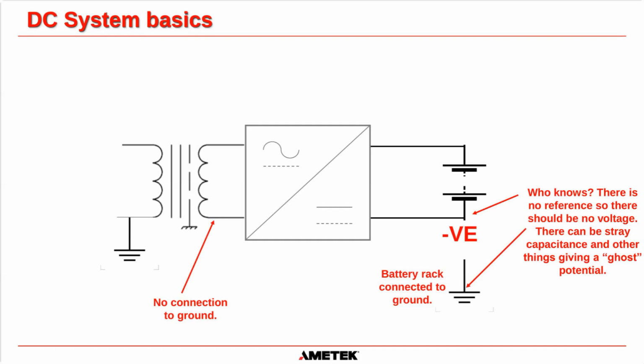And before I do move on, one more reason for why we do this is, remember, battery maintenance is an important part of plant maintenance. So there are going to be people who go out on a quarterly, 6-monthly, annual basis and touch your battery and maintain your battery. Okay, so if they're exposing themselves to the terminals on the battery, and obviously, especially if it's a big battery, they're leaning up against the rack and they're reaching over the rack, you want to make sure that the rack and the battery are completely separated so they can't get an electric shock.